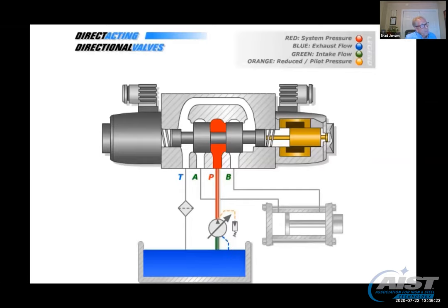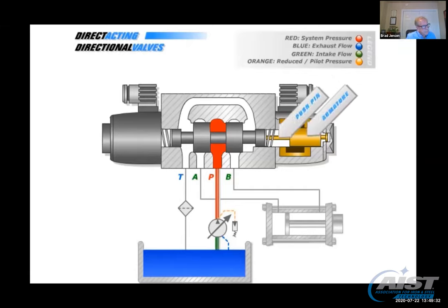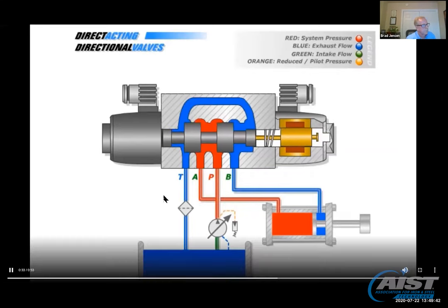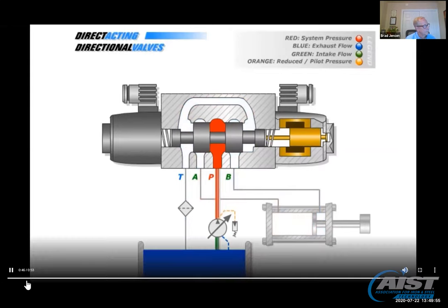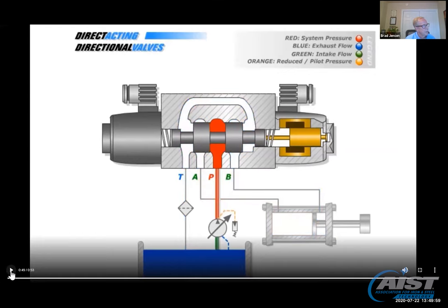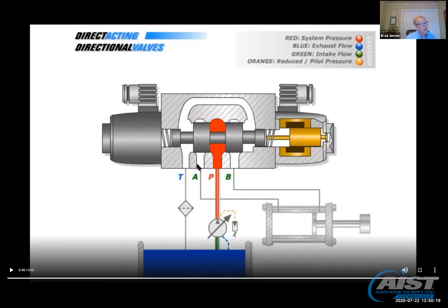In the center position it's blocked. However, the A and B are open to T. We'll talk about that in a second. But right now this coil has been energized. This is where that valve sits. That's nice to know—that's a huge gap. This directional control valve controls the extension retraction of the outboard bearing clamp cylinder. That's what it's doing there. That's what it's controlling. But I want to show you something that has a lot of relevance here. A direct acting directional control valve is either manual or solenoid actuated. Direct acting indicates that some method of force is applied directly to the spool, causing the spool to shift. In this illustration, energizing the solenoid or coil creates an electromagnetic force which pulls the armature into the magnetic field.